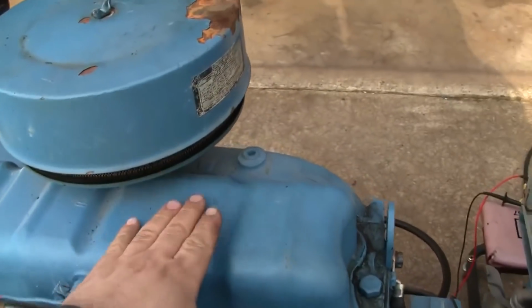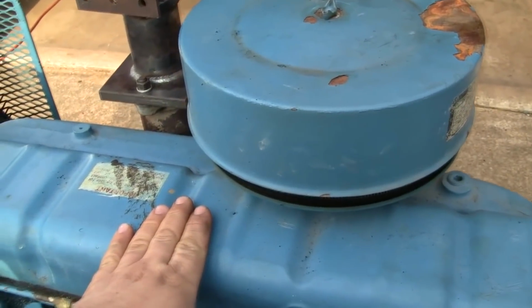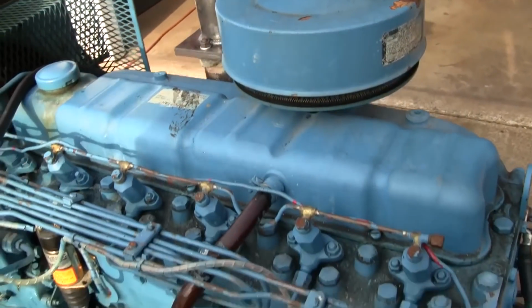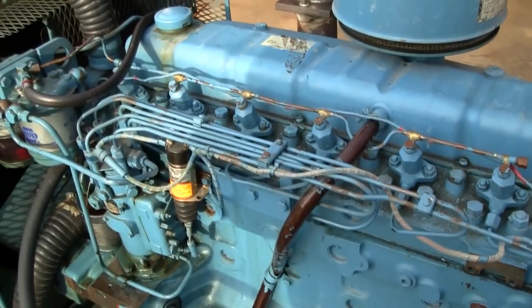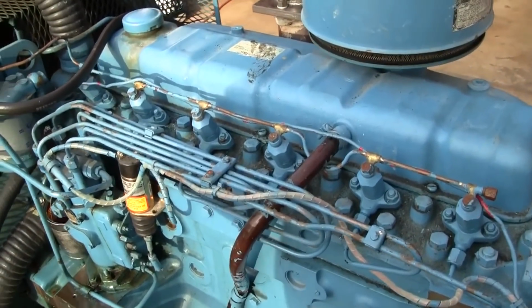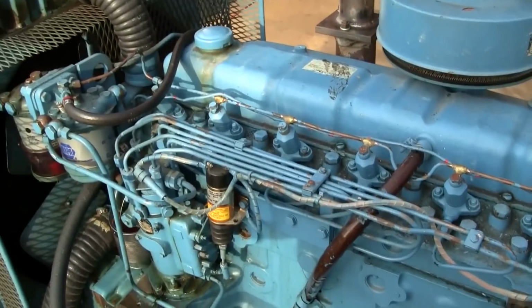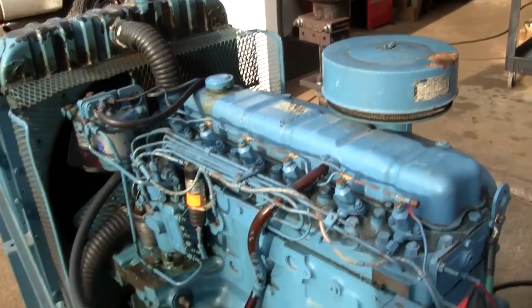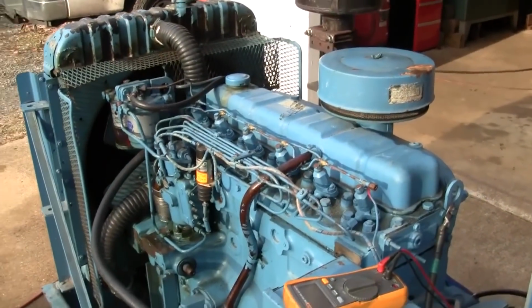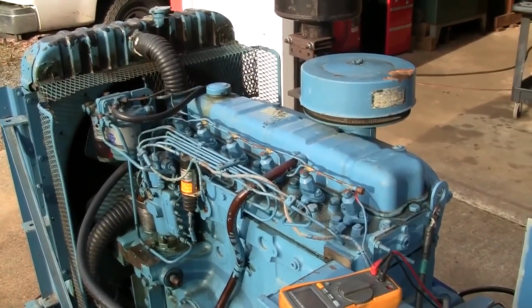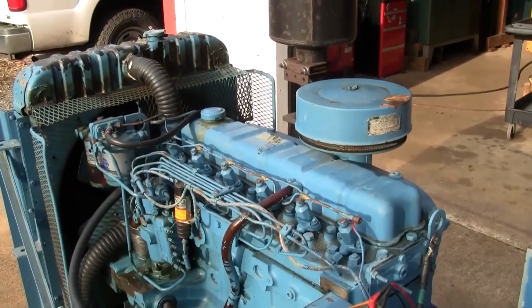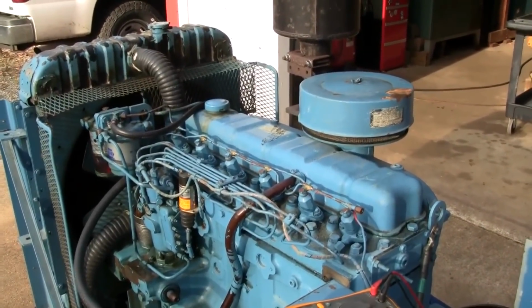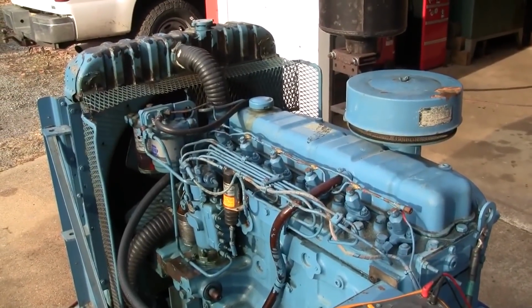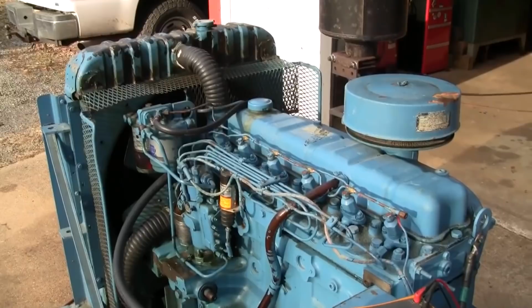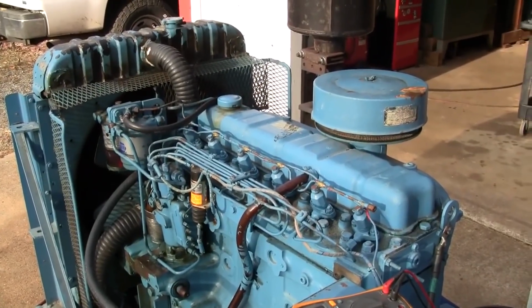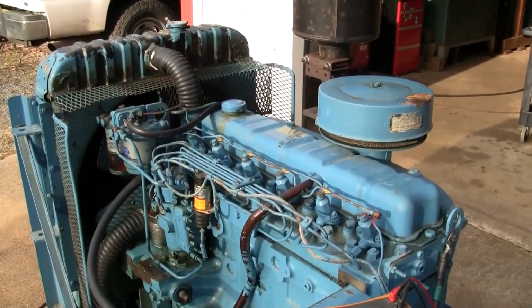I should mention that I already did adjust the valves. The first time I ran this unit with load, I noticed this hesitation, slash misfire. Checked those valves, and turns out they hardly had any clearance at all. So reset those, really no change. So let's go ahead, we'll let it cool down, pop those injectors out, and we'll do a compression test on it.